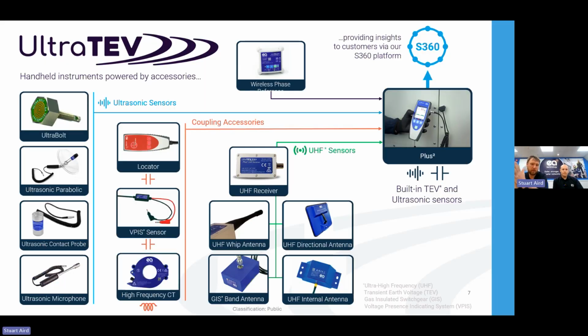Well, the first step is we've expanded the capability of the handheld device. By capability, I mean applicability, which switchgear, etc. this can be used with. So starting with the Plus in the right-hand corner, as you all know, it's got two inbuilt sensors. So we have a TEV sensor inbuilt and an ultrasonic sensor inbuilt. They were primarily targeted at metal-clad switchgear.